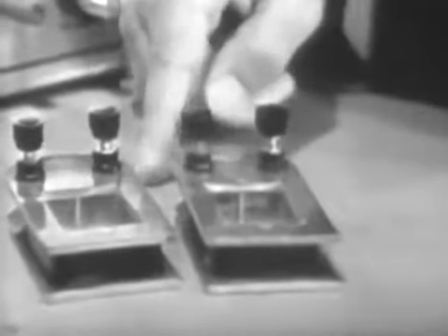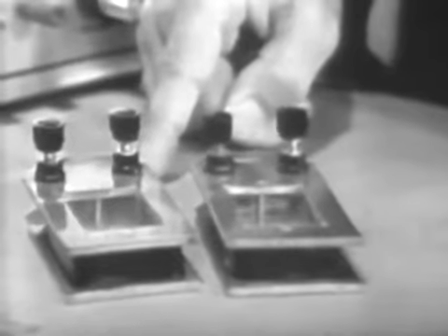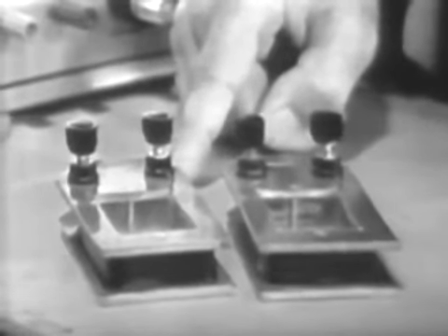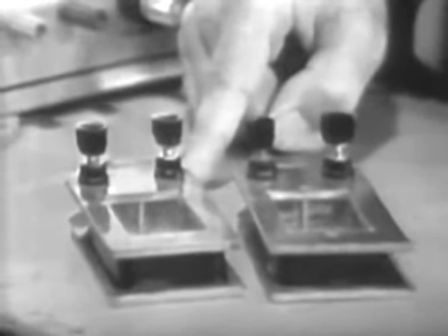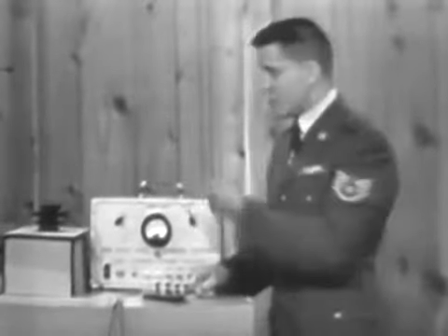This winding has 300 turns. Its normal resistance is 20 ohms. The big difference in these two windings, however, is that one of them is shorted and one of them is open. So let's use our ohmmeter and see if we can tell which is which.